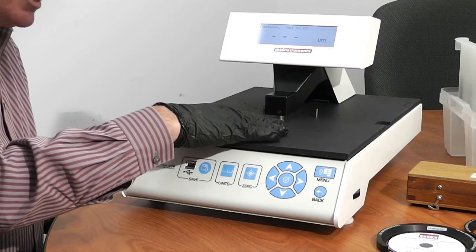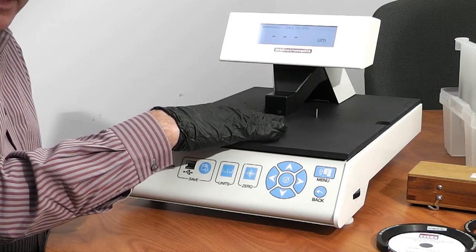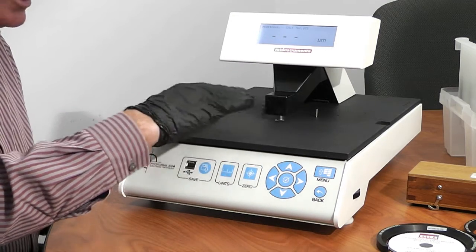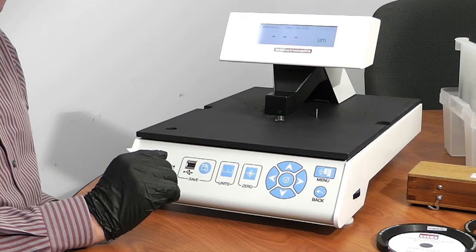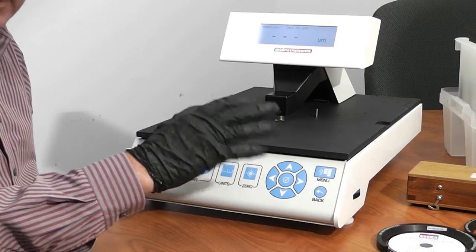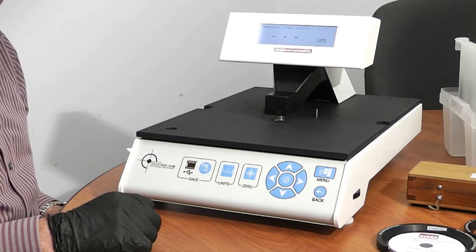The reason we do that is so that when you first place the wafer down, you might have an air bearing situation going on, and you don't want the wafer to shoot off the side. You also want to reduce any residual stresses on the top deck that may create a strain that might affect your reading by, say, a quarter micron or so.